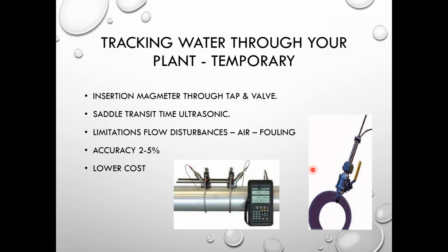So how do we test flow through the factory? How do we test it in a closed pipe? I was talking briefly to you. This is really the only way of measuring flow in a full pipe that's active and at site. And that's by using what we call a saddle transit time ultrasonic sensor, or we have insertion meters. So it's just basically putting a valve and tapping into the line and putting a magnetic sensor down into the flow. And so these two types of flow meters could be used at various locations to basically verify that your flow meter, your full pipe flow meter, is working accurately.